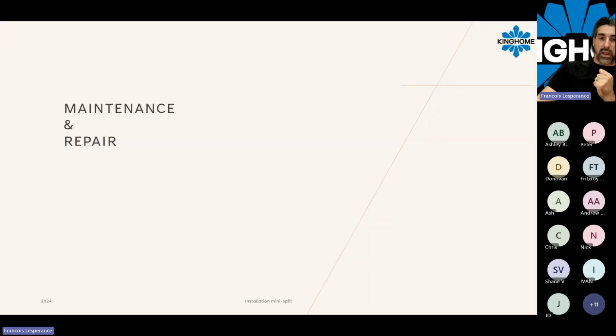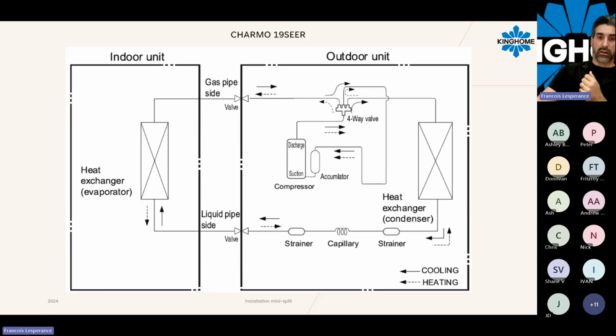So, maintenance and repair. I have for you here a bunch of diagrams that we will look at together to explain what the refrigeration circuit for a ductless system looks like. We start here at the compressor. You have the discharge line directly here, and the discharge line is connected directly to the four-way valve. The four-way valve is the device that changes its inner portion to make the system go in cooling mode or heating mode. For this example, we're going to stay in cooling mode.